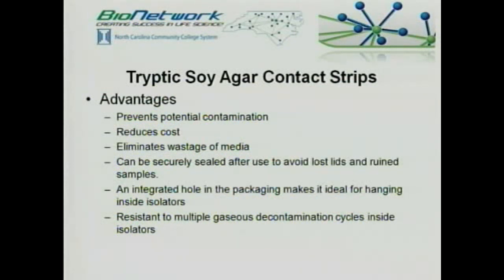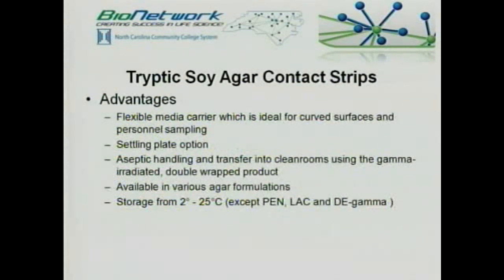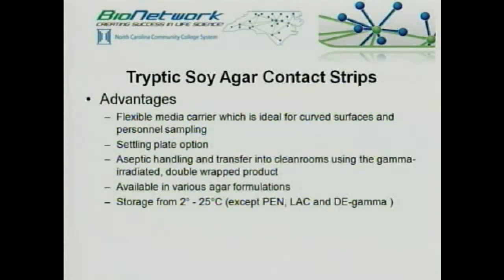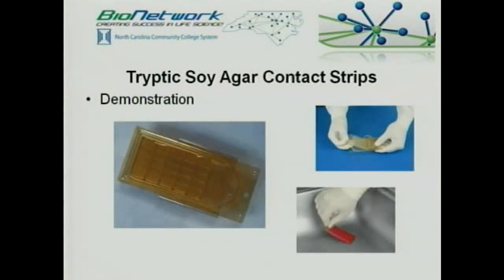They're securely sealed after use so there's no risk of dropping a plate or cross-contaminating lids. They have an integrated hole in the package for hanging in an isolator environment. They're resistant to gas decontamination cycles used in isolators. They're flexible for curved surfaces and can be used along the inside of rounded vessels. They can also serve as settling plates by turning the agar side facing up. Since they're gamma-radiated and sterile, decontaminating just the outside makes them ideal for transfer into clean rooms. Available in different formulations, stored at room temperature up to 25 degrees Celsius.